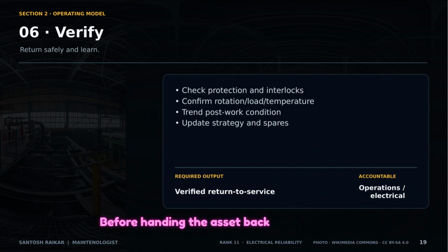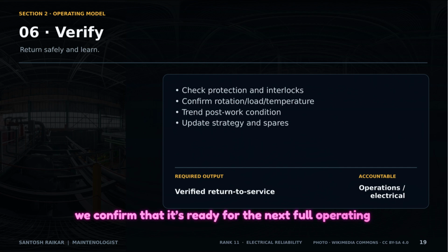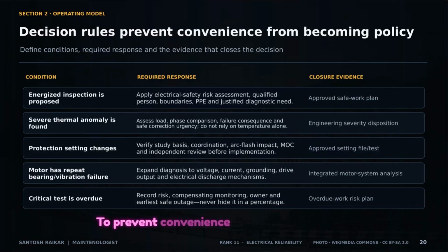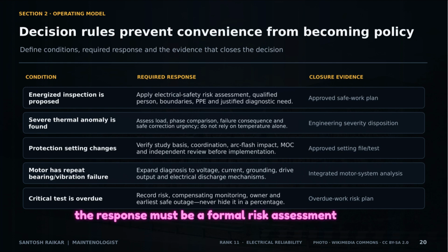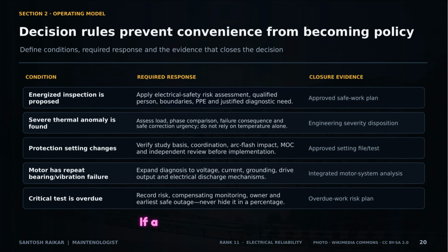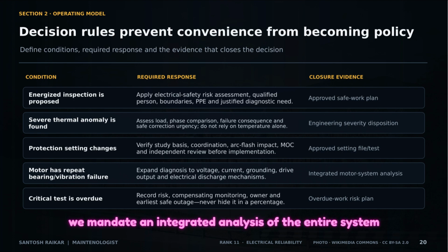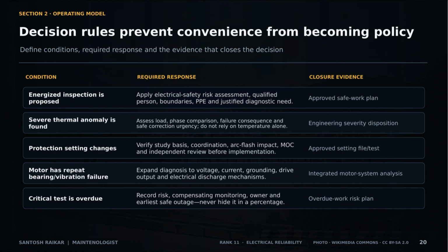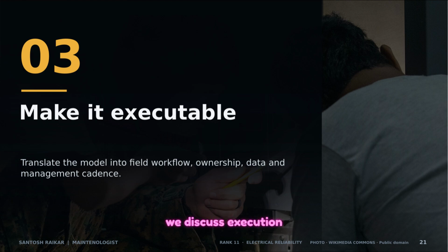Before handing the asset back to operations, we verify phase rotation, protection settings, and load stability. We don't just fix it, we confirm that it's ready for the next full operating cycle. To prevent convenience from replacing policy, we use clear decision rules. For instance, if someone proposes energized inspection, the response must be a formal risk assessment and a safe work plan. If a motor has a repeat failure, we mandate an integrated analysis of the entire system, not just a bearing swap.